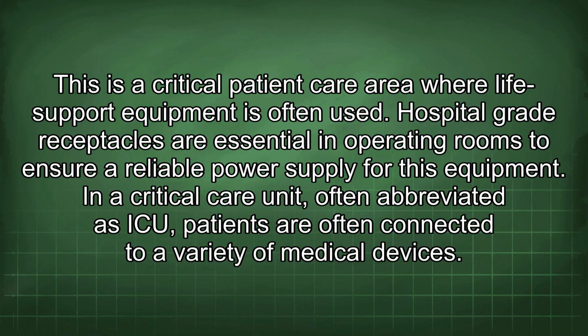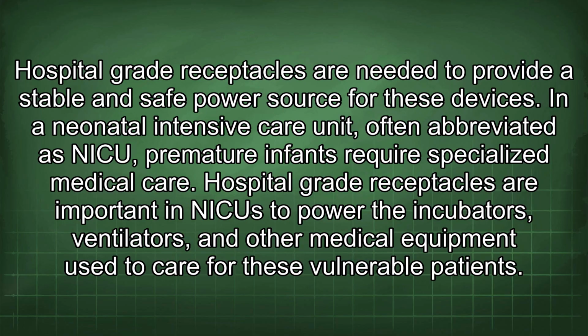Hospital-grade receptacles are essential in operating rooms to ensure a reliable power supply for this equipment. In a critical care unit, often abbreviated as ICU, patients are often connected to a variety of medical devices. Hospital-grade receptacles are needed to provide a stable and safe power source for these devices. In a neonatal intensive care unit, often abbreviated as NICU, premature infants require specialized medical care.